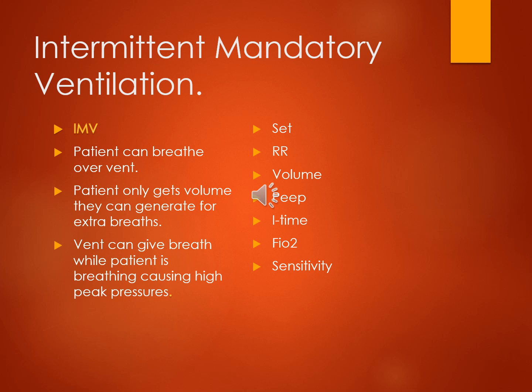Well, here's the big dangerous caveat to this mode of ventilation. When they're cycling their breath, they'll get whatever volume they can generate. So say they generate 200 mLs, now the ventilator time cycles, and it's giving 500 mLs. So that 200 now goes to 700. So we don't want that to happen. So that's why we're not using IMV. But it's good to know where we were so we can know where we're going. All right. On to the next one.